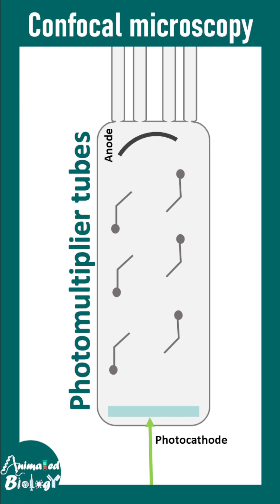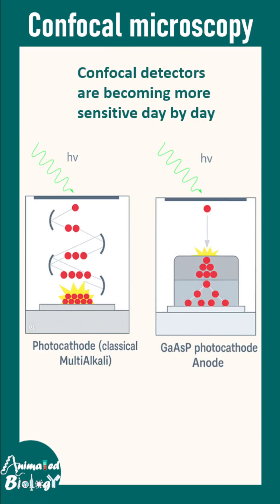In confocal microscopy, photomultiplier tubes (PMTs) are used as detectors. The PMT has a photocathode where photons from the specimen strike, leading to the emission of photoelectrons. These photoelectrons travel through an array of electrodes called dynodes, each more positive than the previous one, leading to amplification of even faint signals.